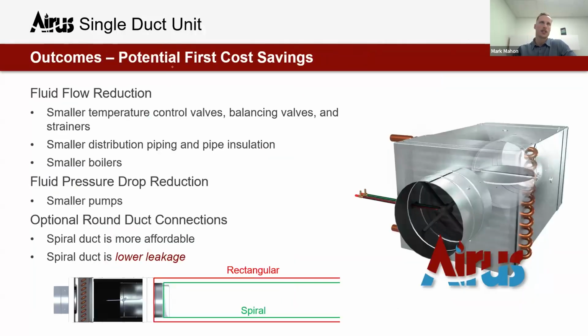And then there are some great potential first cost savings. So of course, with fluid flow reduction, we're going to see smaller temperature control valves, balancing valves, and strainers, smaller distribution piping and pipe insulation, the potential in some cases for smaller boilers. Not in all cases, that would depend on some specific boiler selection fundamentals. We are going to see a smaller fluid pressure drop for smaller pumps. We're going to see also a nice benefit of this, potentially a round duct connection. We have round and rectangular slip-in drives, both as standard on the product.